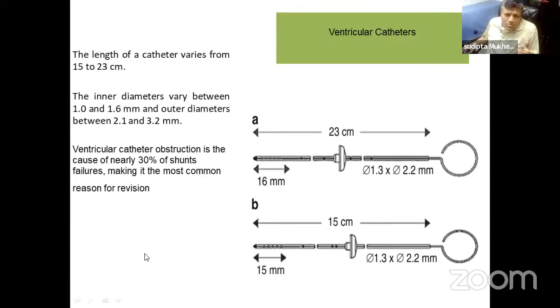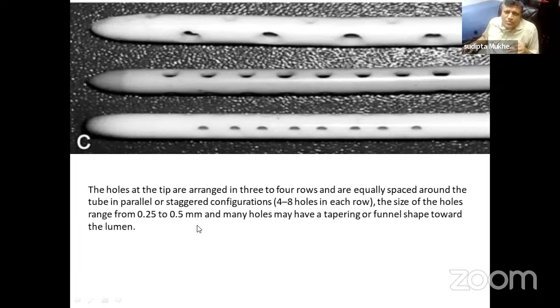It has flanges. It has an expandable ball in the tip. So this is a typical ventricular catheter where the tip contains 3 to 4 rows of equally placed holes, 4 to 8 holes in each row, and a 0.25 to 0.5 millimeter tapering end. Distal catheter. Distal catheter length varies from 90 to 120 centimeter. Inner diameter is almost like the ventricular catheter, 0.7 to 1.3.